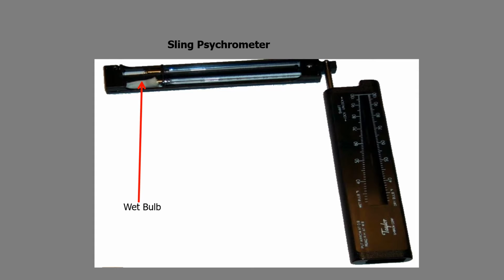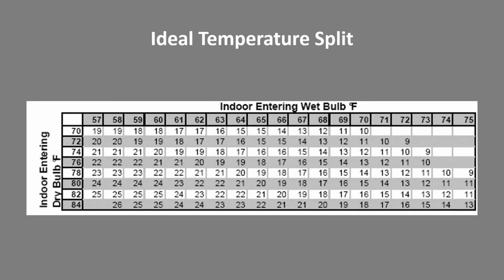If it's really dry, you get a lot of evaporation off the cotton sock, which lowers the temperature of that mercury. If it's really muggy, you don't get so much evaporation. So when it's dry, you get a big difference between the dry bulb and the wet bulb. And when it's muggy, you don't get much difference at all. So all of us have probably heard that, hey, that air conditioner is getting us a 20-degree split.